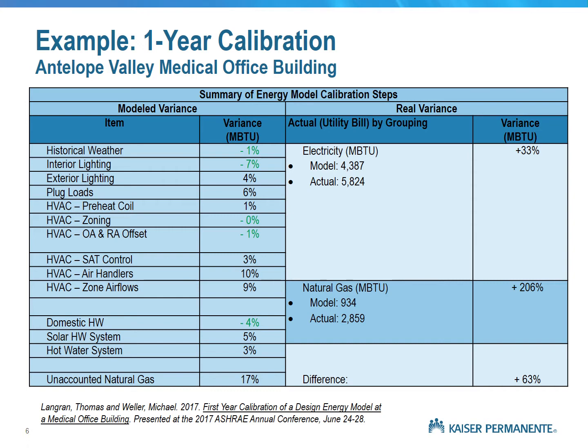The biggest variance in this building is unaccounted for natural gas. And I think after we published this report, we have accounted for it. Every time you start and stop a boiler, you lose about a quarter of the nameplate in BTU as a cycling loss. And so in this building, the heating load is like 1,000 MBTU, and we use 3,000 MBTU, which is to say we spend twice as much natural gas cycling the boilers as we do heating the building.